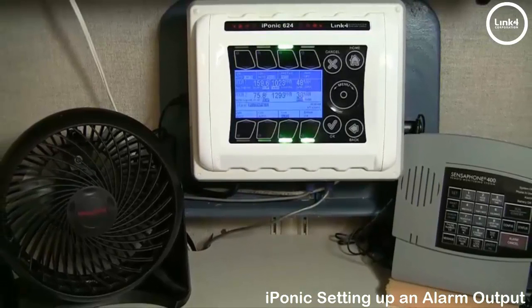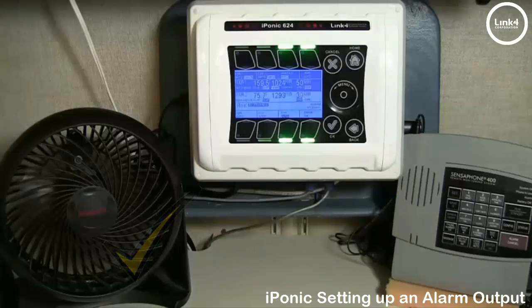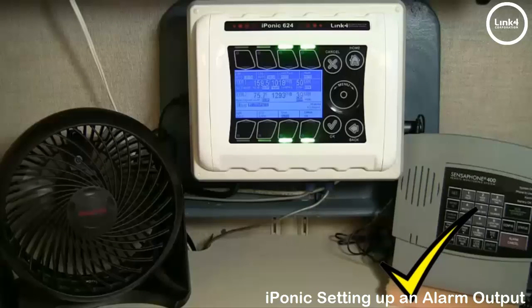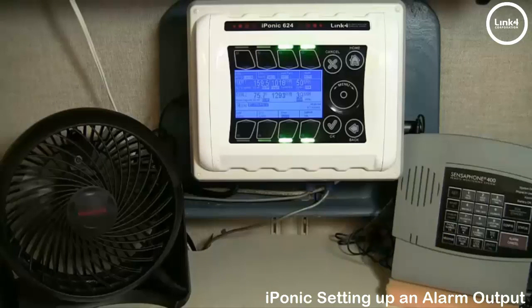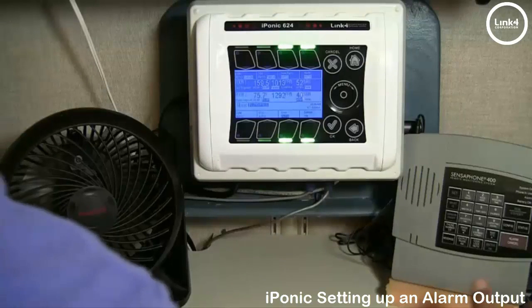Our high temp alarm engaged, and immediately the vent fan turned on, and our alarm output engaged on number 4. Zone 4. Zone 1 high temp alarm. And our Sensaphone engaged as well. 50 degrees Fahrenheit to 5. Zone 1. Zone 1 high temp alarm.